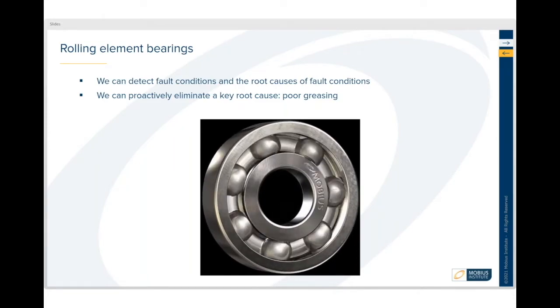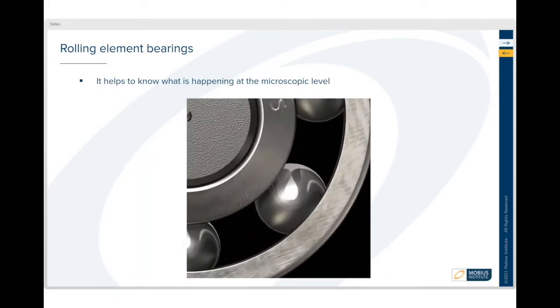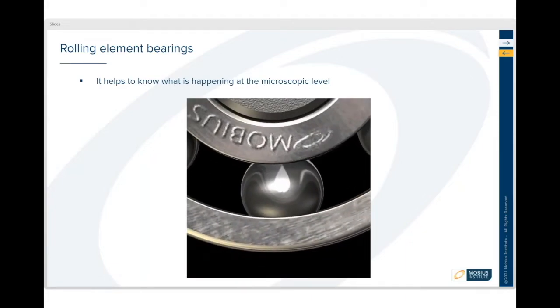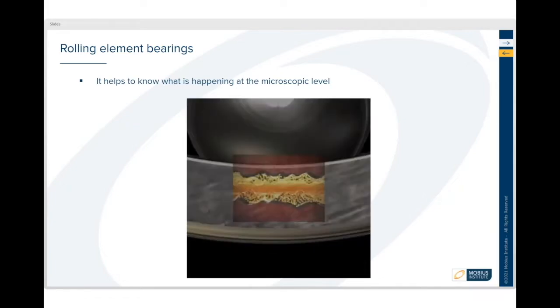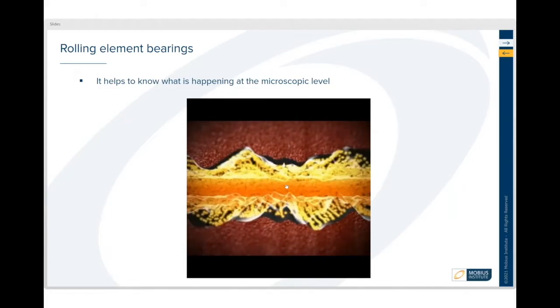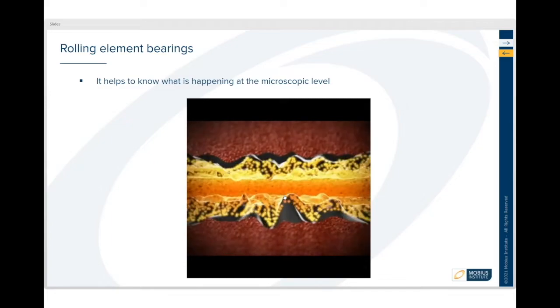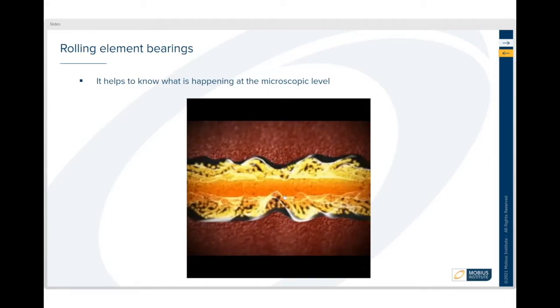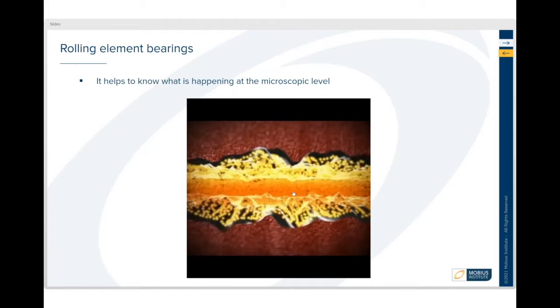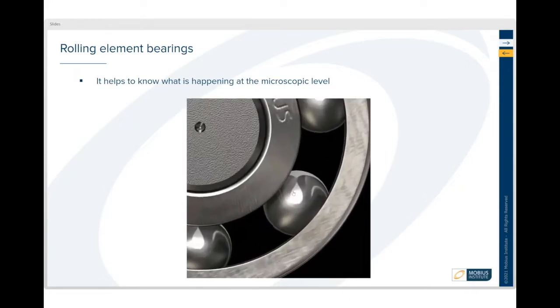It's just important to understand what's happening inside a bearing because we might think of them as being pretty tough, steel and all. But if we get down to the microscopic level, there's less than a micron, a millionth of a meter—a meter is about a yard if you're that way inclined. But as those surfaces come closer together because there's a lack of lubricant, the sound will change. If there's damage in there, the sound will change but it'll be periodic.